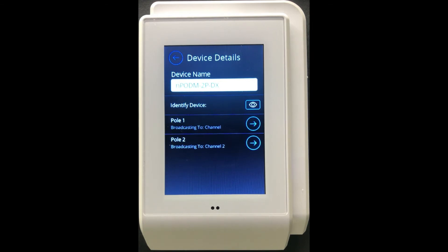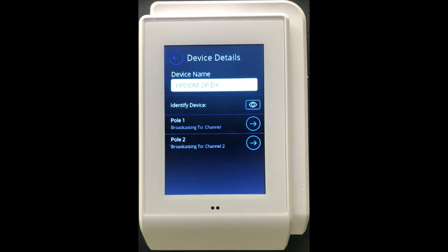When you tap Identify, the LED indicators on the wall switch will blink, allowing you to effectively determine and confirm which switch is being identified. This device is a two-pole device, so you can associate the first pole to a specific channel and the second pole to a specific channel as well. As a reminder, input devices broadcast to channels and each pole can only broadcast to a single channel.